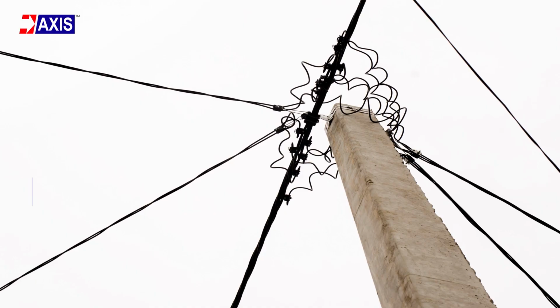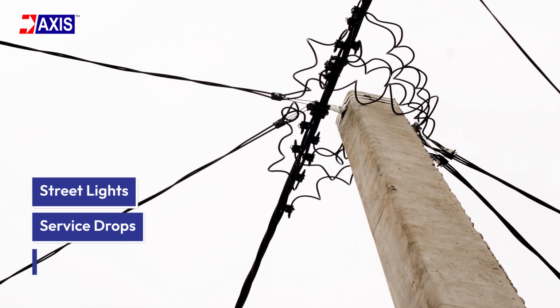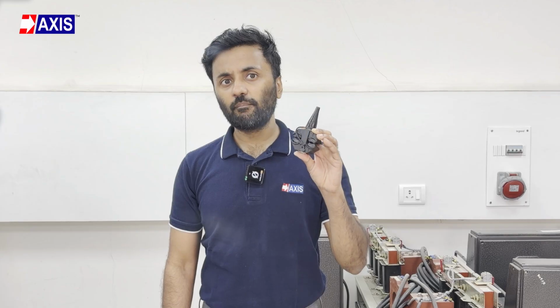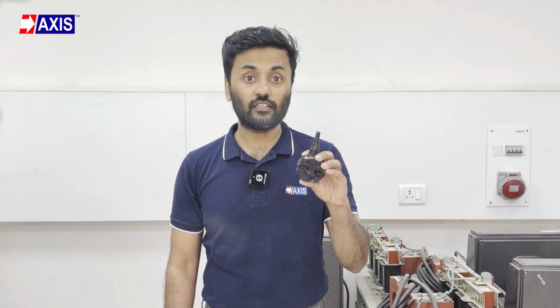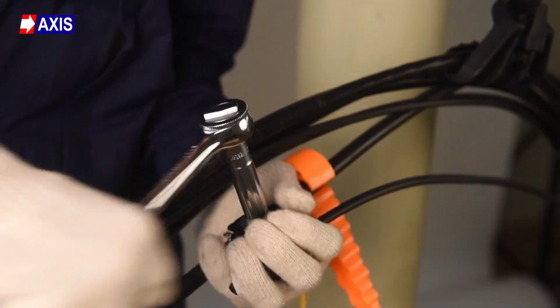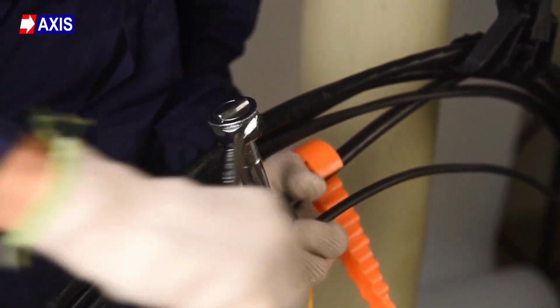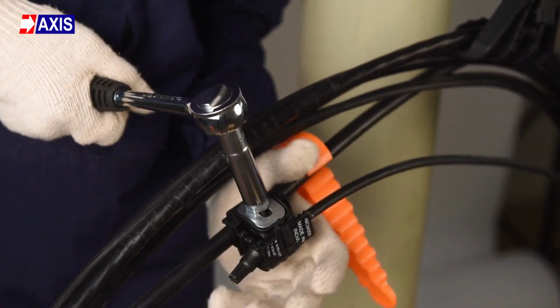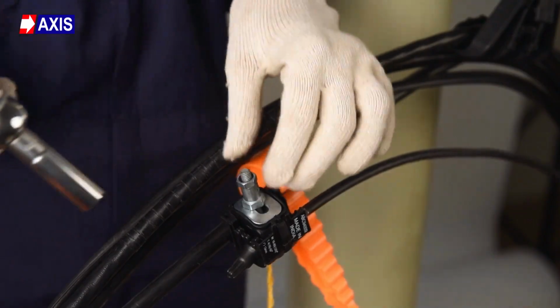On the other hand, IPCs are built for quick taps and branching. You use them for street lights, service drops, and distribution lines. The application demands speed and sealed protection. An IPC pierces through the insulation to contact the conductor, and no stripping is needed. You only need a simple wrench with torque control. The shear head bolt breaks off at the correct torque. As a result, installation is easy.